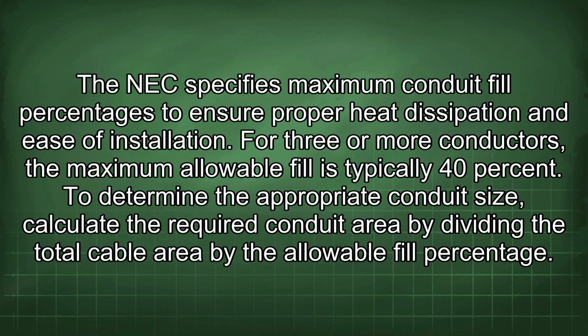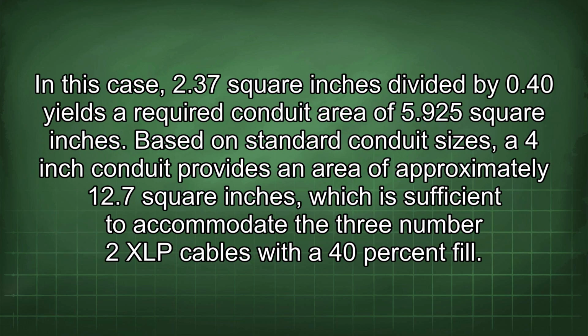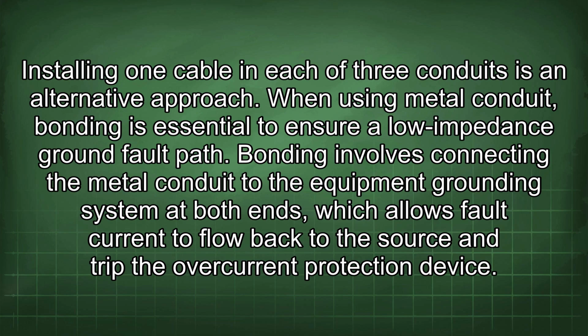To determine the appropriate conduit size, calculate the required conduit area by dividing the total cable area by the allowable fill percentage. In this case, 2.37 square inches divided by 0.40 yields a required conduit area of 5.925 square inches. Based on standard conduit sizes, a 4-inch conduit provides an area of approximately 12.7 square inches, which is sufficient to accommodate the 3 number 2 XLP cables with a 40% fill. Installing 1 cable in each of 3 conduits is an alternative approach.